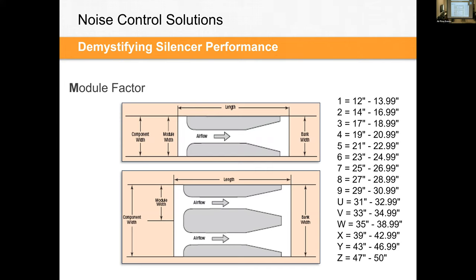Chris, when you build the silencer, I see like you could take the top one and overlay it on the bottom one and you'd have the same thing. Do you ever build it with baffles? We do often, yeah. So the top one would be called a one module factor. One there. So the top one would be called a one module silencer. The bottom one would be a two module silencer. Not the module factor, just the number of modules. So we would often build units like this where they have a center pod or center baffle and then two side baffles. We'd also build them with three.